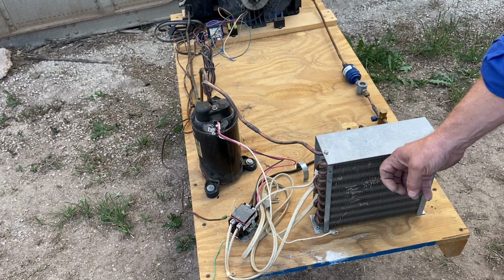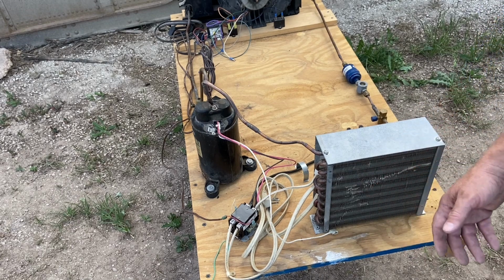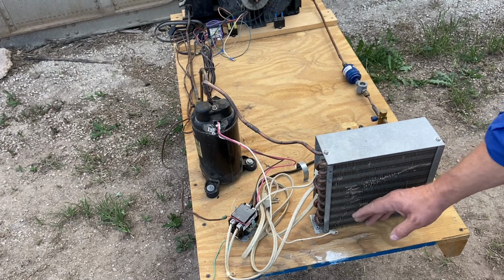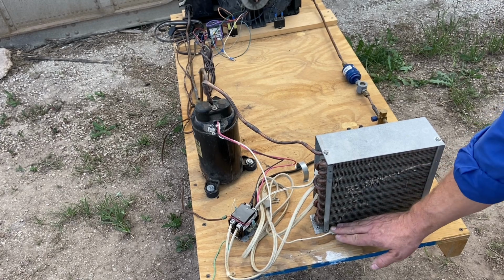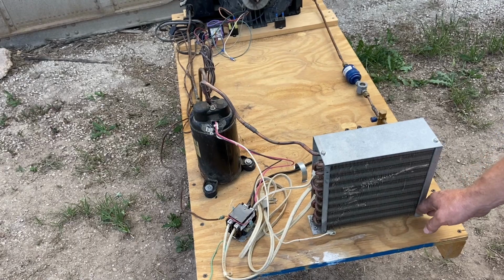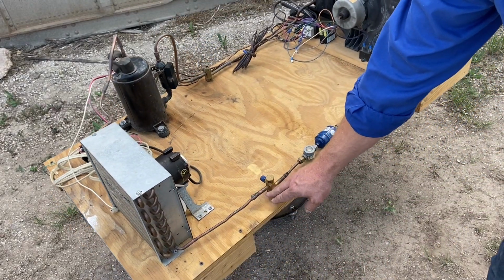As it changes state from a vapor to a liquid, it's rejecting massive amounts of BTUs of heat out of the refrigerant. But it's going to be the same temperature because it's latent heat. All that saturation. Below saturation, we now subcool it. We take even more heat out, but that heat is sensible. So now we leave the condenser as a subcooled liquid in our liquid line.